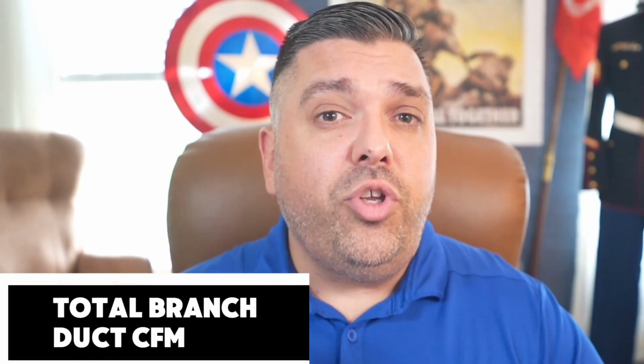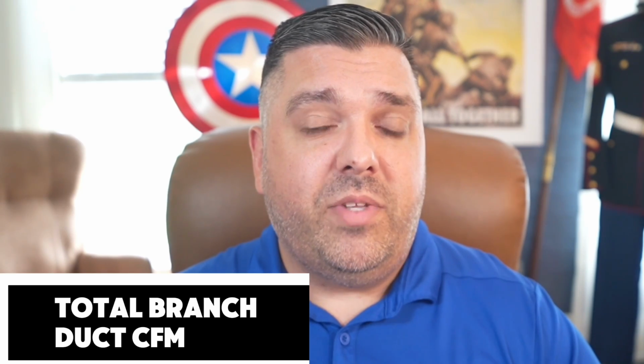This is where measuring static pressure becomes your best friend. If you're seeing high supply static with low return static, you've probably got a restricted supply system. This could be undersized ducts, it could be a restrictive coil, it could be loose duct liner clogging the airways, right? Step 4, total your branch duct CFM. Here's your final verification. Add up all the CFM capacity of every branch duct. This total should equal or exceed your new system's design CFM.